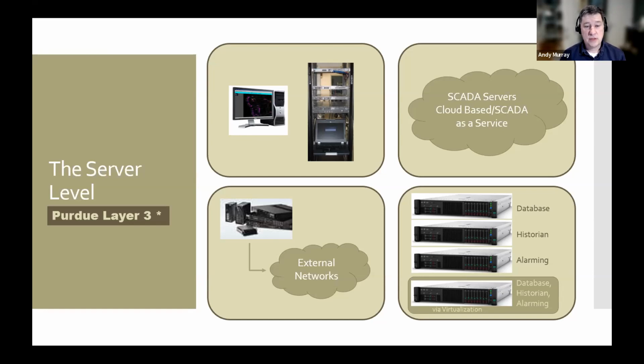But again, at the server level, the SCADA systems that I typically work on are smaller. So it may just be one SCADA server, which is really just some Dell desktop, or two for redundancy. Bigger systems may have not only redundant servers, but may also separate out functionality. They may have a server that is the database, so the real-time data from the SCADA system goes to one server. Then they have a separate server for a historian, where a subset of that data is logged, especially the analogs. You could have a separate server that's also doing alarming.